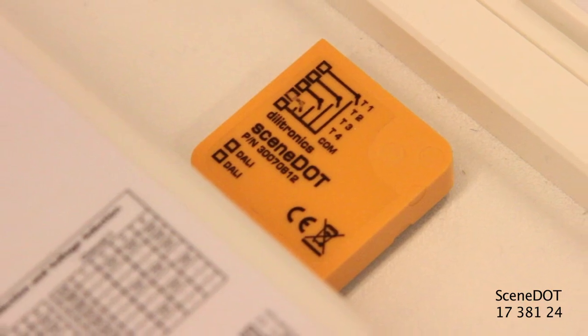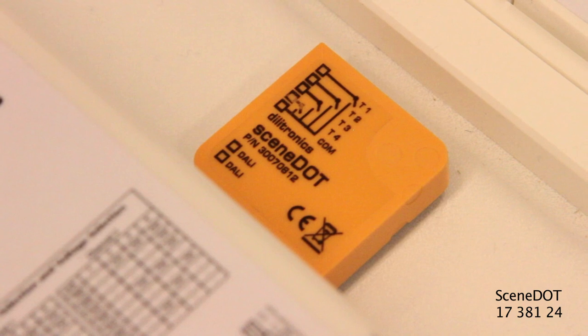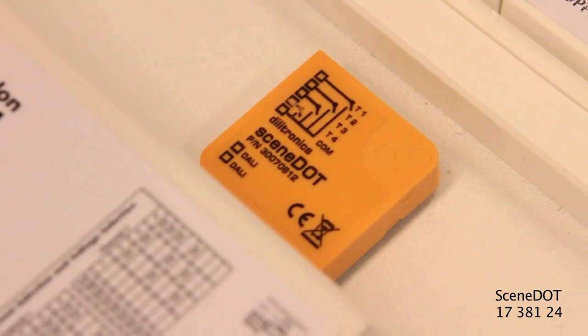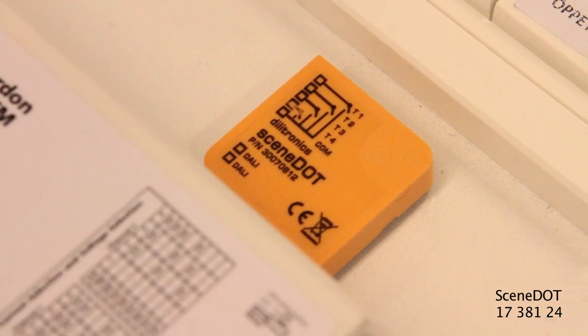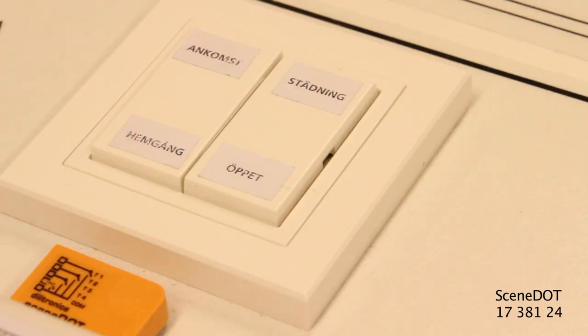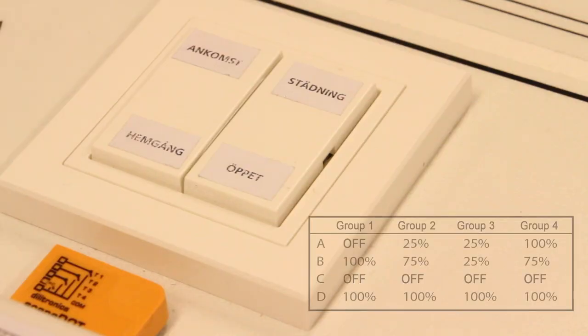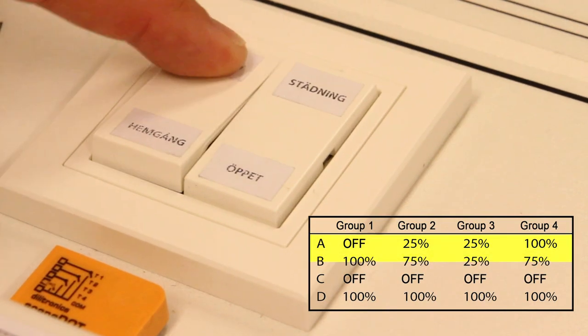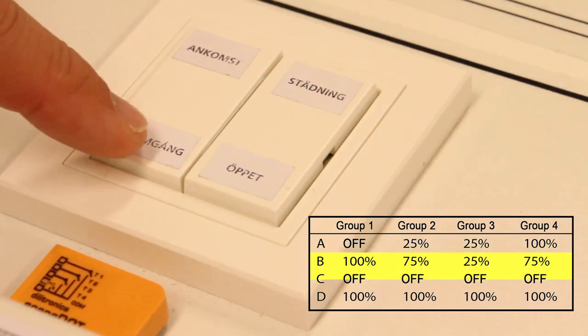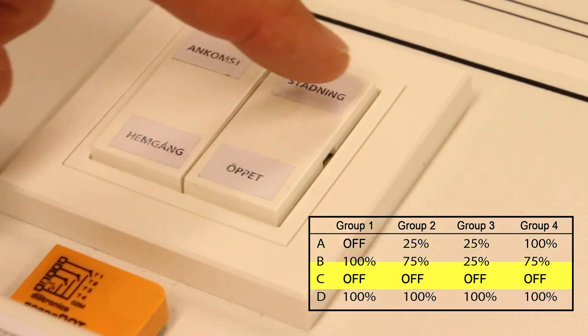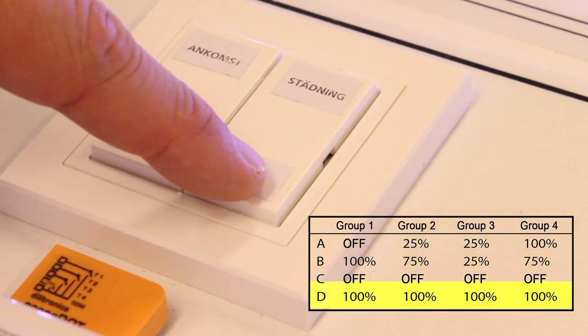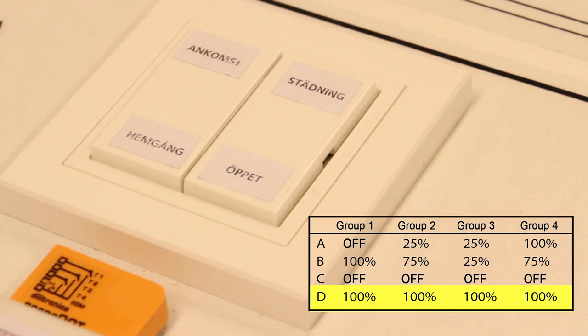Scene dot enables the function to store and recall up to four scenarios. Scene dot is an interface between a momentary push button and the DALI bus. Four buttons can be connected to the module, one for each scenario. For achieving the best results, using a four-channel low-volt switch is recommended.